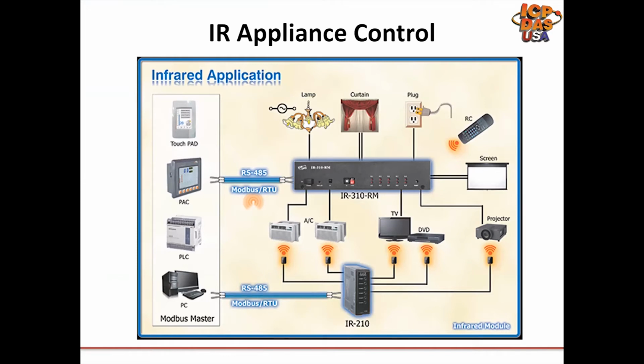These IR modules come in two different communication methods, Modbus RTU and Modbus TCP, meaning they communicate either over a serial line, that is RS-232 or RS-485, or over an Ethernet network, usually Cat6 Ethernet cable. Being the most common network in our line of work, we have more options for Modbus RTU devices.